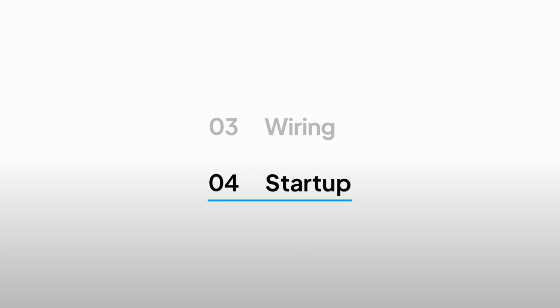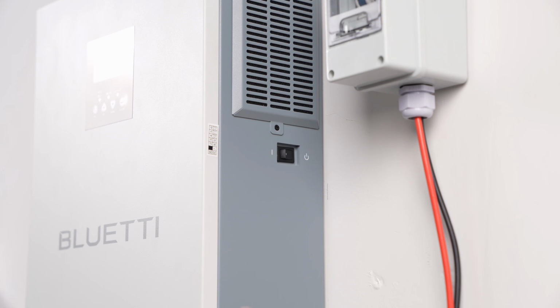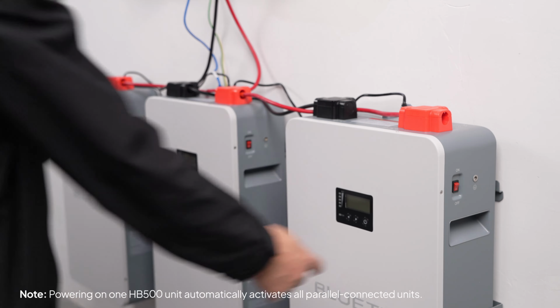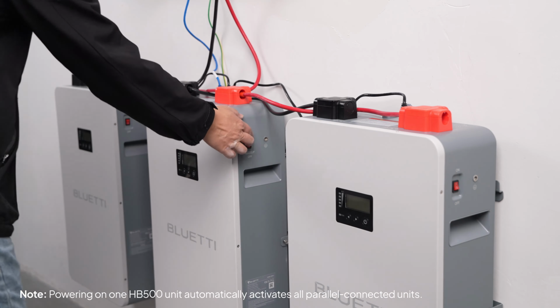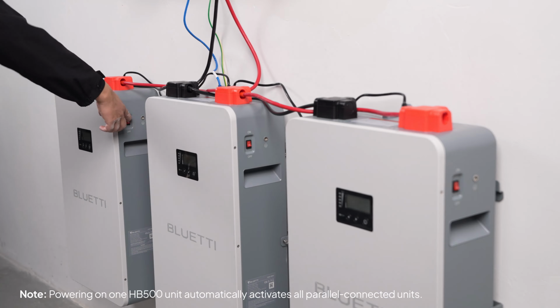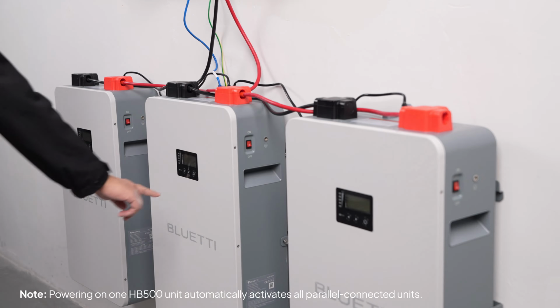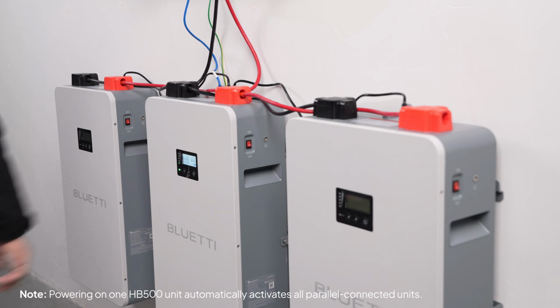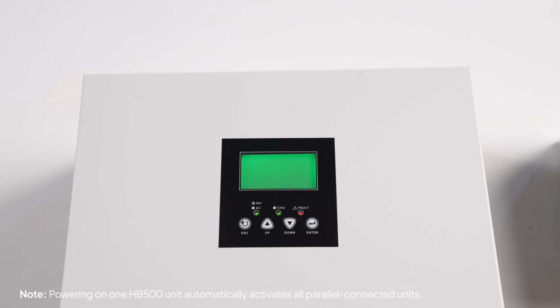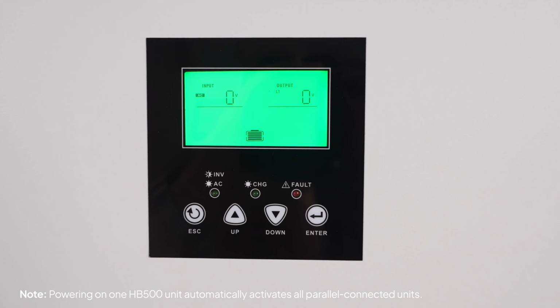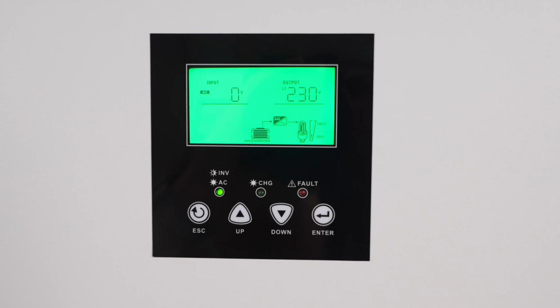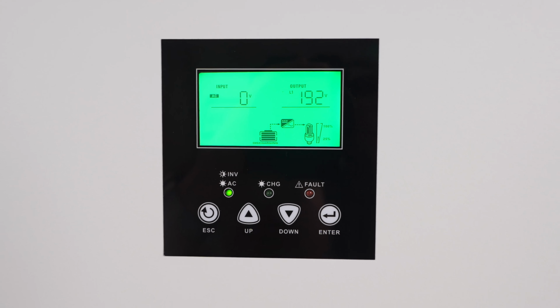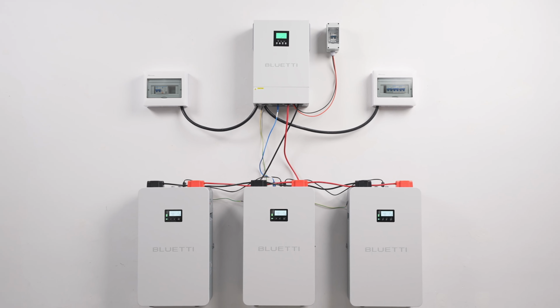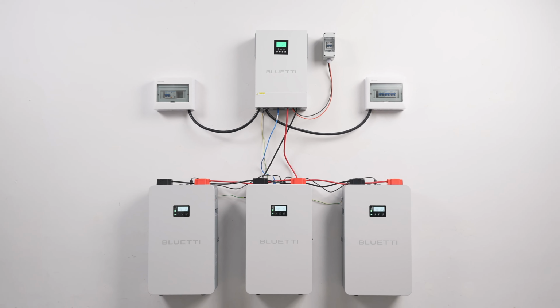Now press the on-off switch to start the inverter. Then set the emergency stop switches on all batteries to on. Press and hold the power button on one HB500 for 1 second. It powers on and the other batteries start up automatically. When the inverter's status and charging indicators turn green, the system is operating normally. That's it. Your HV10K and HB500 system is ready.